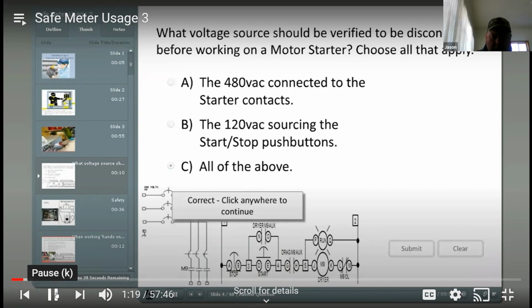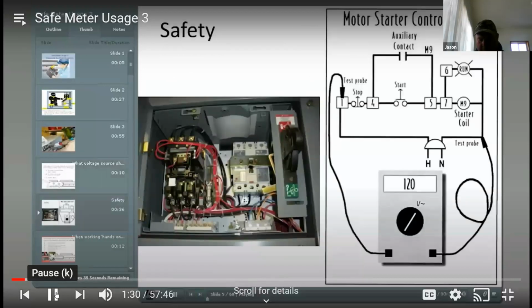The correct answer is C, all of the above. The 480 volt AC connected to the starter contacts and the 120 volt AC sourcing the start, stop, push buttons. Properly verifying this helps in the troubleshooting and repair process. The meter is also used to confirm that a circuit is safe to work on when touching components that were once energized with voltage. Sometimes a component like a starter is supplied with voltage from two different sources. This means that tripping the disconnect supplying the 480 volts AC to a starter contactor does not disconnect the 120 volts AC being supplied to the start-stop control terminals on the motor starter circuits.